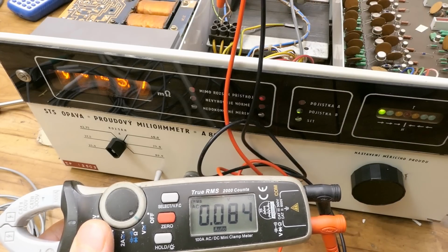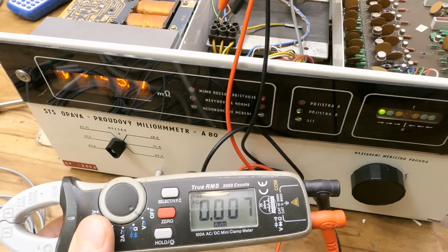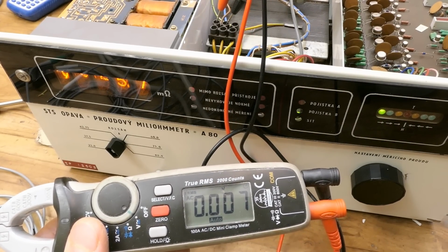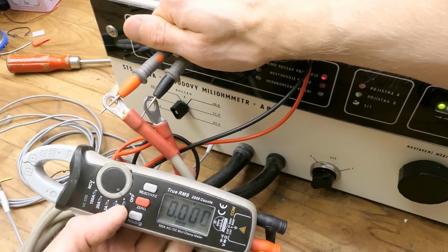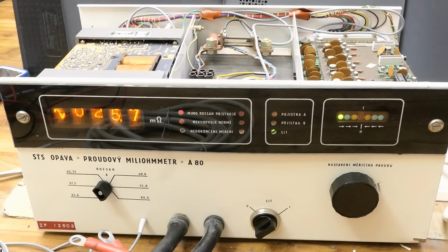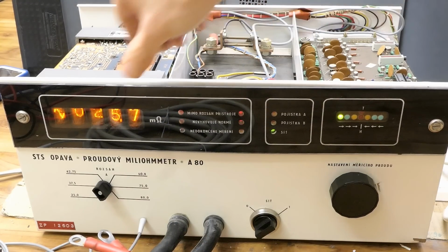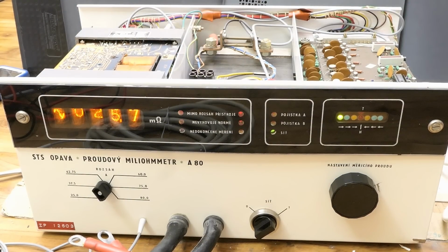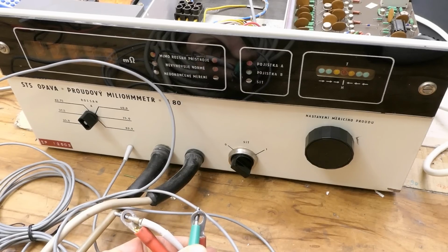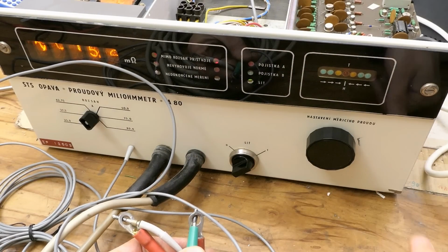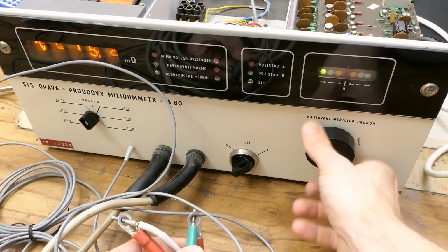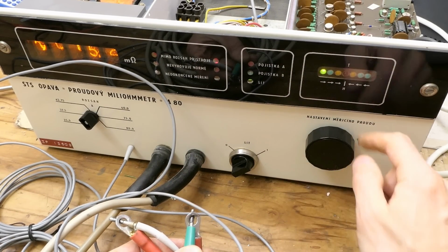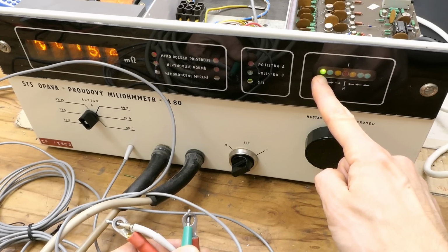Nothing. And the live and neutral of the terminal block of the big transformer, again no voltage. And also the two measuring cables showing no voltage. It seems like the control circuitry of it and the panel meter are working, but the power section not. If I connect this pair to this pair, still nothing. This indicator is stuck at the first LED.